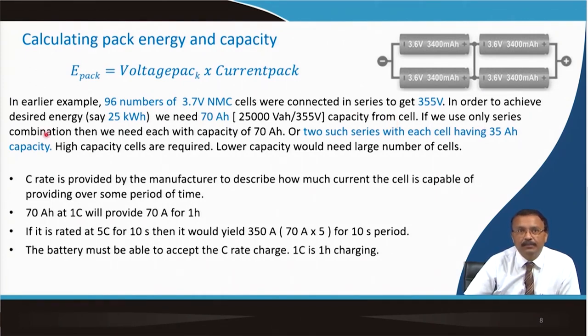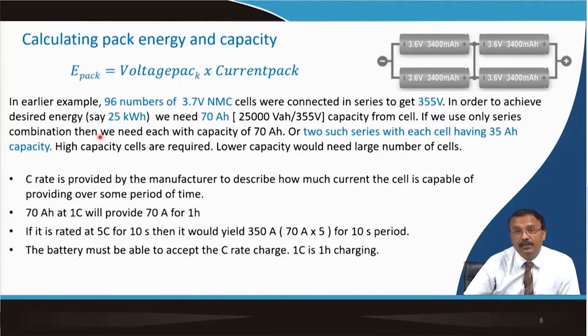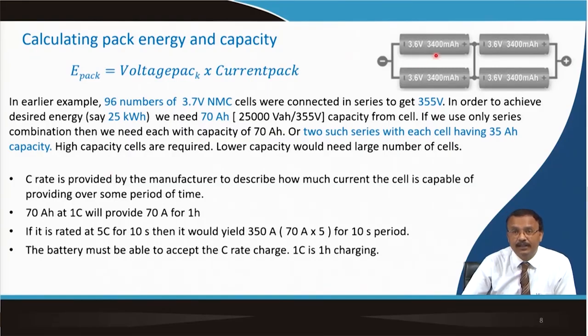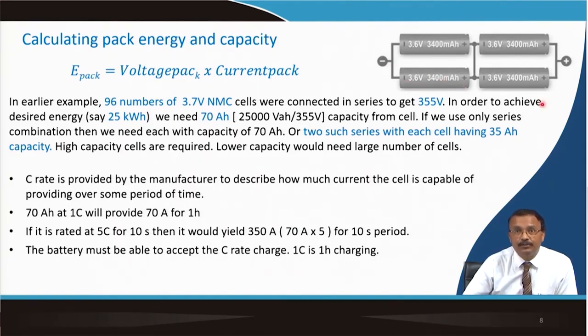Using only series combination, you need 70 ampere-hour cells. Alternatively, you can use two parallel series strings each with 35 ampere-hour cells to achieve the required capacity. High-capacity cells are preferable; lower capacity cells require a larger number of cells. Cylindrical cells can provide around 3.4 Ah at 3.6 V. Various configurations are possible to achieve the desired capacity level.